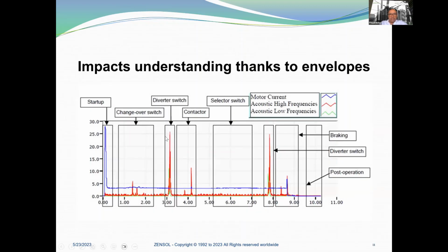So, impact understanding thanks to the envelope. Here you can see the motor current envelope, and in red, for example, you have the impact of the diverter switch here, the selector switch, which is silent, the diverter switch again, and here this is the braking part that you can see here. When we are able to understand these kinds of curves, then you are sure that you understand exactly what is happening in your tap changer. This part sometimes takes time, but it's a good effort to do.